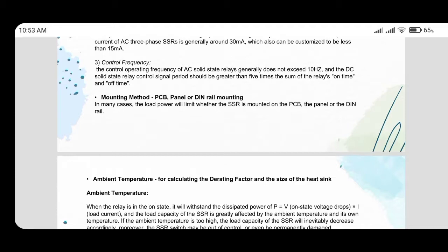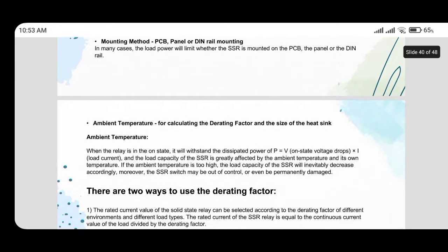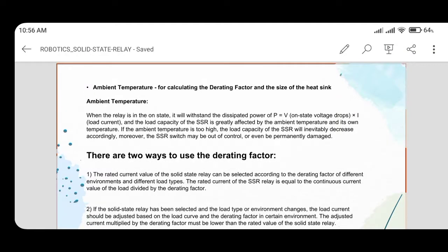Ambient temperature for calculating the derating factor and the size of the heatsink. When the relay is in the on state, it will withstand a dissipated power of P equals V, the on-state voltage drop, times the load current. The load capacity of the SSR is greatly affected by the ambient temperature and its own temperature. If the ambient temperature is too high, the load capacity of the SSR will inevitably decrease accordingly. Moreover, the SSR switch may go out of control or even be permanently damaged.